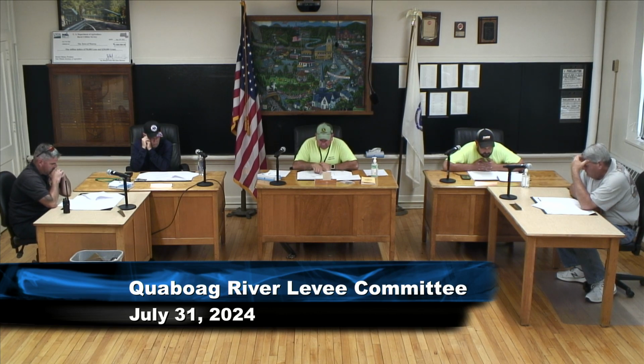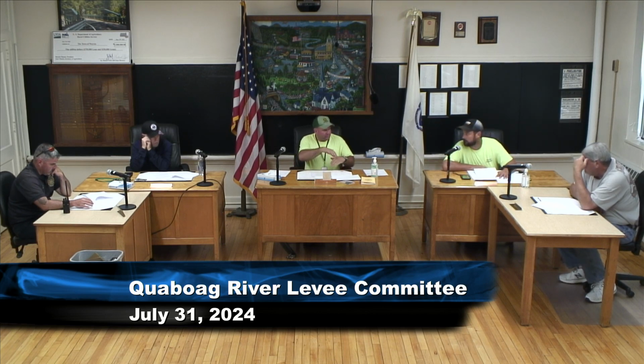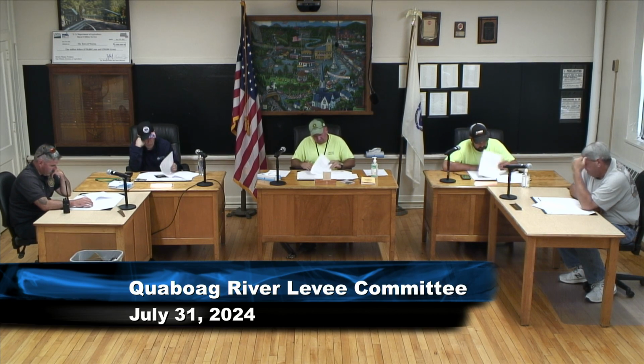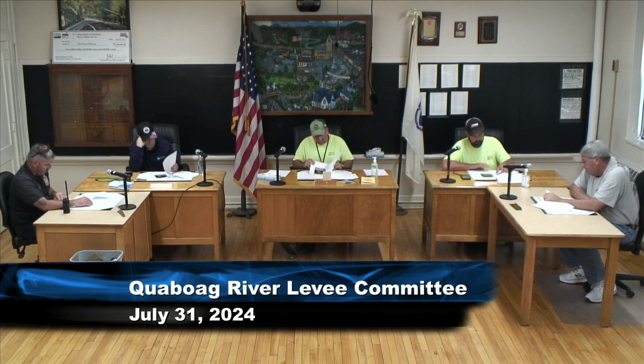Attached, you'll find some photos below, and a brief description of the conditions found in the manholes upon entering and exposing the valve location. They did do a little bit of shoveling to get around some of them to get better pictures. Valve 1 seems to be in working order. The valve chamber needs to be cleaned. Look at some of these attached pictures for 1 and 2.